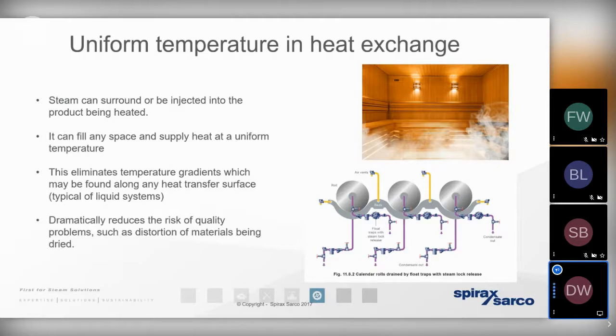But we also know that steam gives up its heat energy equally and evenly across the entire heat transfer surface area. And we're trying to demonstrate that in the little picture that you can see up in the top right of the screen. It's a sauna. Well, if we put 2 or 3 kilograms of steam into a sauna, as a gas, it's going to spread out and it's going to occupy all of the heat transfer space. But if we put 2 or 3 kilograms of water into the sauna, it'll just sit there in the bottom of the sauna as a puddle. It's not using that heat transfer space very efficiently at all.